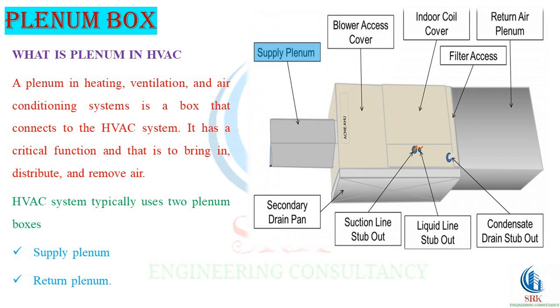A supply plenum works by taking in the new cool or warm air from the heater or air conditioning system and, in turn, distributing it throughout the building using the HVAC's ductwork. A return plenum takes in that used air and, using the ductwork, sends it back to the core HVAC system. That air is recycled as a fresh batch later.